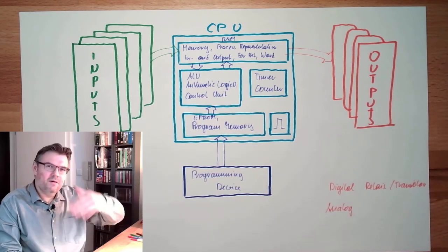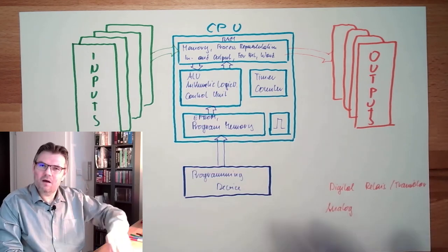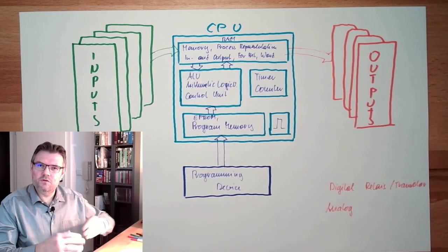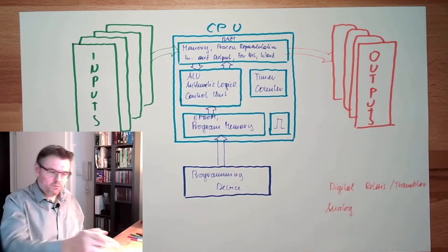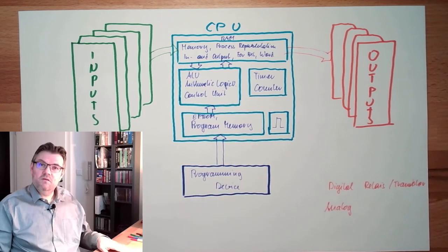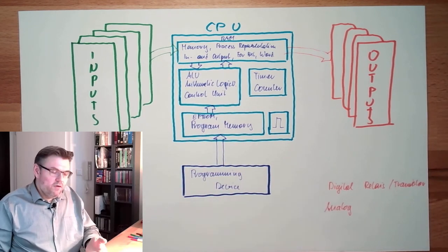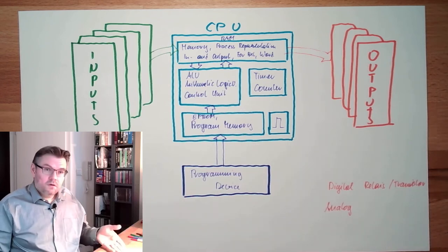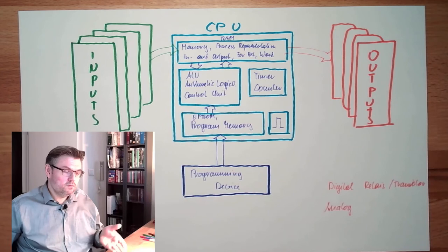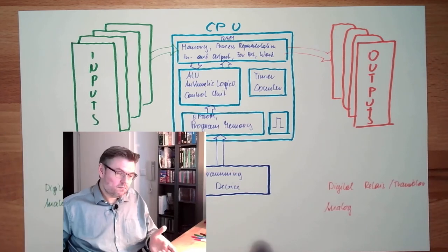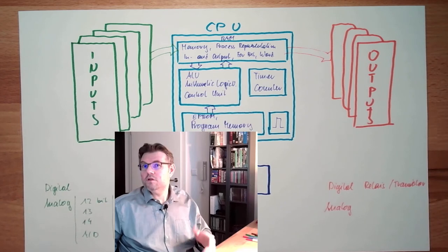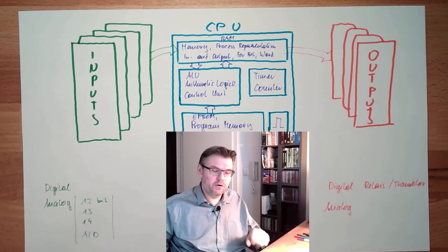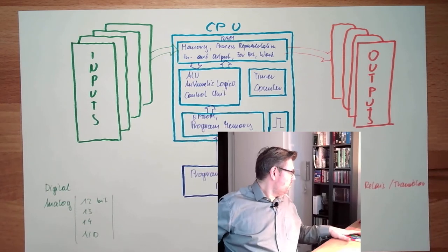So there is no connection in between. The digital output might be relay or transistor, usually transistor output. And there are also cards with 8, 16, 32 outputs and so on, and each output has a certain address. I give the number, it will write. Analog output pretty much is the same like the analog input. Now here it's a digital analog conversion with a certain resolution, also then depending how much money you spend and what is really necessary. Also 12, 13-bit is very usual value.